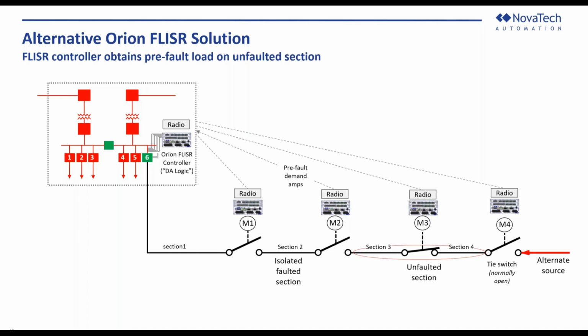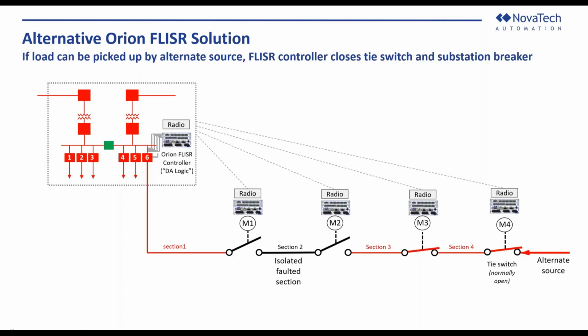If the load can be picked up by an alternate source, the FLISR controller at the substation will close the tie switch and the substation breaker, so we can have the service back on for sections 3, 4, and section 1. So all the customers that are not being impacted by the faulted section can have service restored, and that minimizes the overall impact of the fault.